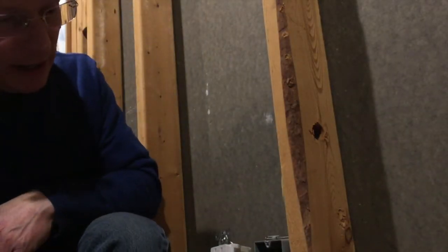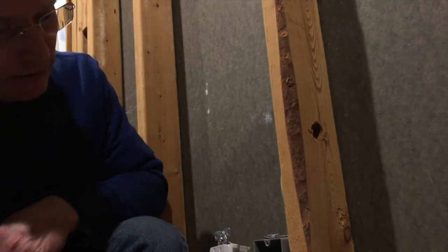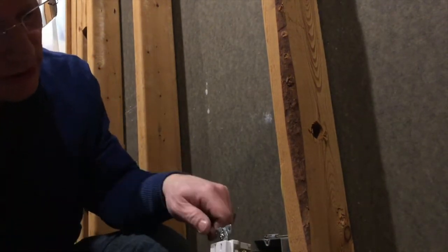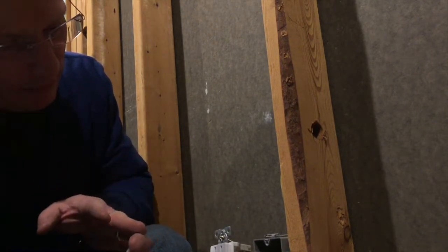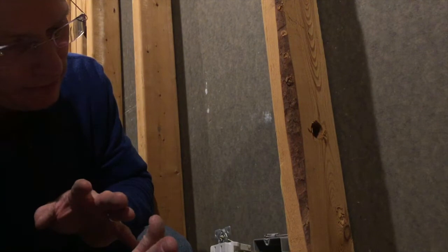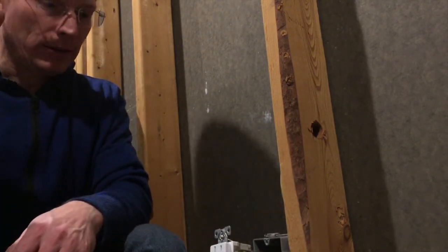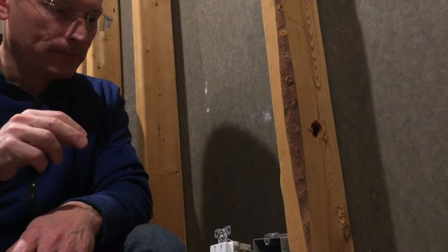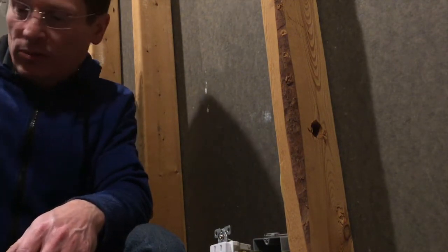Turn back on the power. You can see my GFCI has a light on here. Light indicates that it's in fault condition. So I'm going to reset it. Okay, and it didn't pop. All right, that's good. Now I've eliminated 1, 2, 3 outlets as causing the fault. Now I'm going to take my light over to that outlet, that third one, and verify I'm getting electricity.